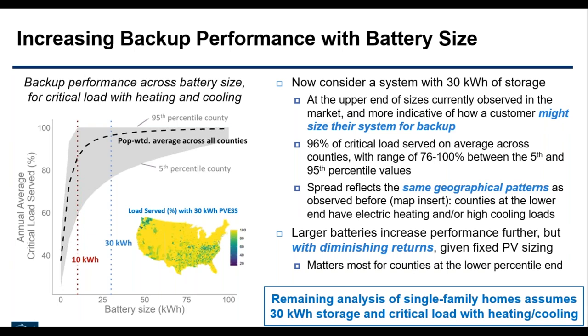When we analyze this in a parameter sweep of battery sizes, we see that larger batteries allow for larger portions of critical load being served, but there are diminishing returns. This gives a sense that from an economic perspective, if we were to find a sweet spot, it definitely would not be at the very large size of battery.